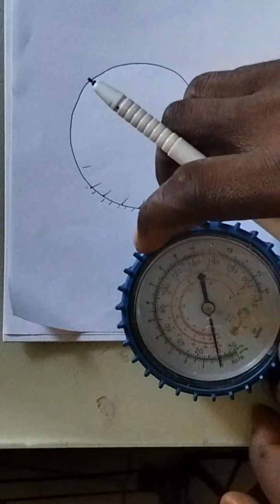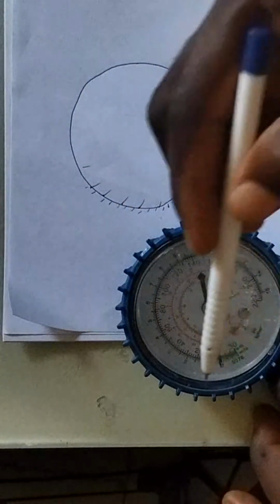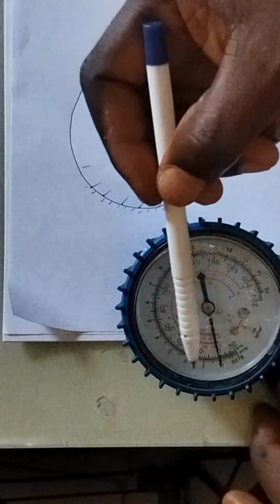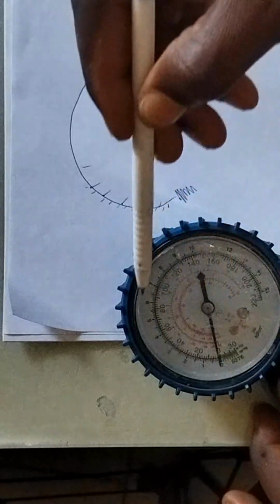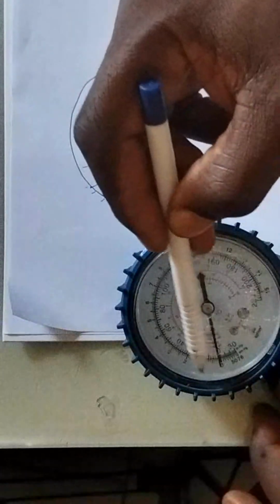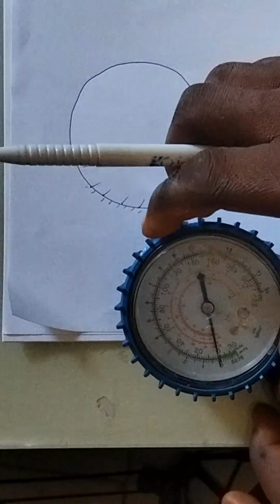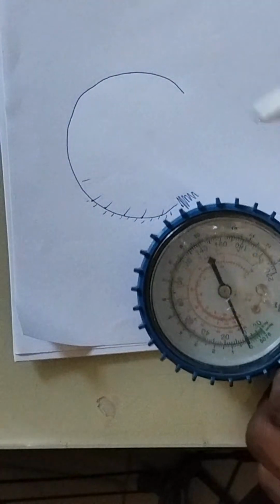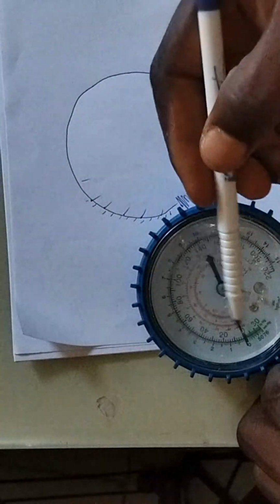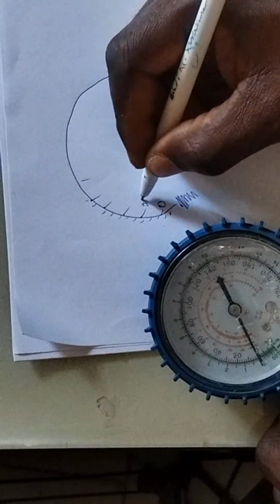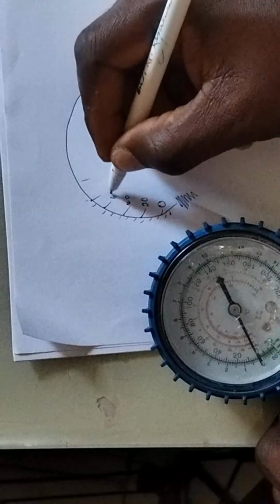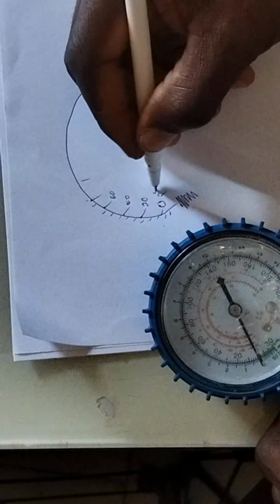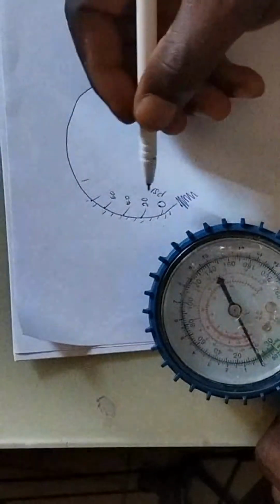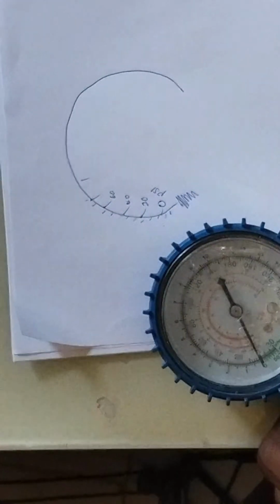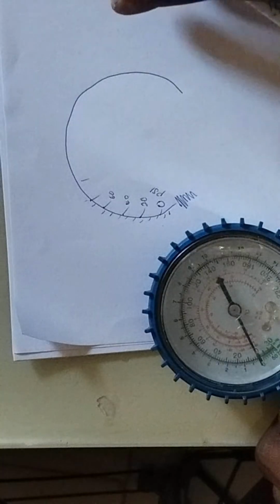But with this single gauge manifold, this kg doesn't actually work here, understand? The outer calibration, which is the outer numbering here, doesn't work on this single gauge manifold. What you see working on this single gauge manifold mostly is the inner calibration. This inner calibration starts from 0, moves up to 20, 40, 60. Now this is the PSI reading, depending on the kind of refrigerant you are charging.